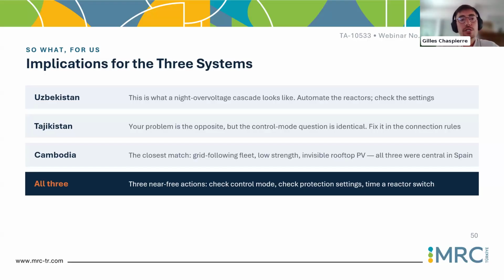overvoltage. For Tajikistan, the problem is most of the time the opposite. But okay, regardless of an over or under voltage issue, if you don't have a proper control mode for your converters, and with more and more converters entering your system, it's important. It will be the same, because in terms of undervoltage, if your converter is tuned in a proper way, it will be able to inject reactive current into the system to bring it up. In terms of overvoltage, it's the opposite, but it's the same principle. You need a quick fix, a quick check.